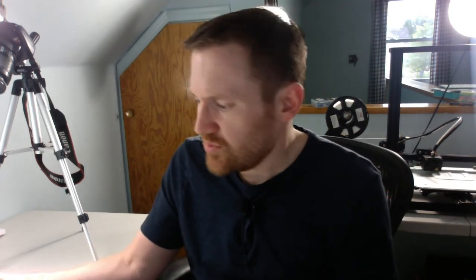With only the camera itself connected, I'm seeing a very similar image issue. So I think what we're looking at is a defective CCTV module. The microscope itself works great — I'm very, very satisfied with the build quality. I'll have to contact the manufacturer and hopefully they'll quickly issue me a new CCTV camera. It did take about a month for this to arrive, so I'm hoping we don't have to wait quite so long for a replacement part.